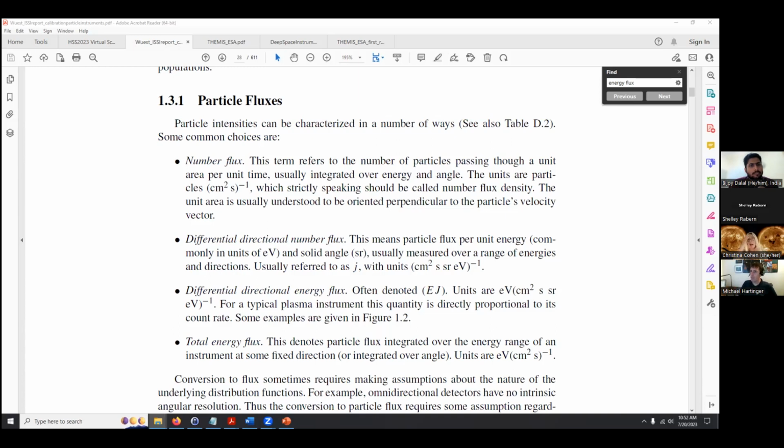And then there are other things where detectors themselves age and become less responsive to, say, the energy range, which is your detector response function. It could be that initially when you built it, your detector had very low efficiency for, say, a 1 MeV particle, but does really great for a 10 MeV particle, and the response function looks nice, like a step function. And then as it ages, that sags. So now your efficiency at 10 MeV, which used to be near 100%, has sagged down to like 70%, and that will start affecting how many of those particles at 10 MeV you can actually measure.